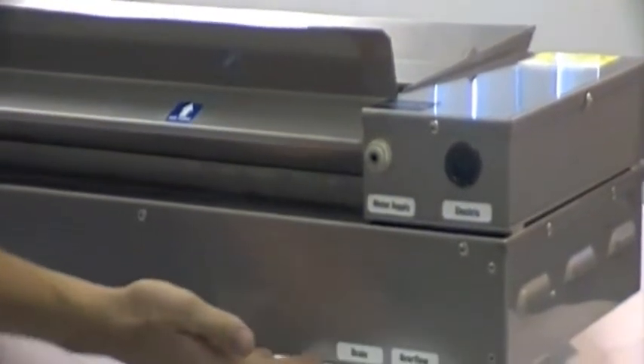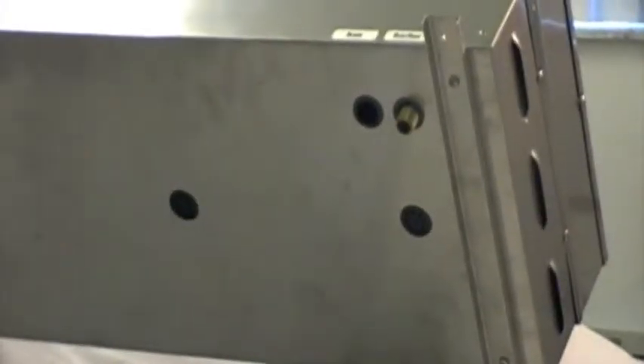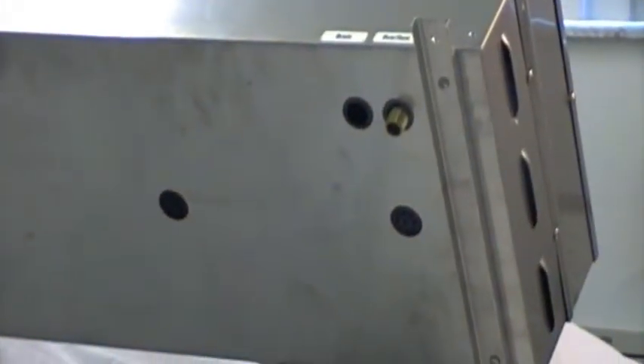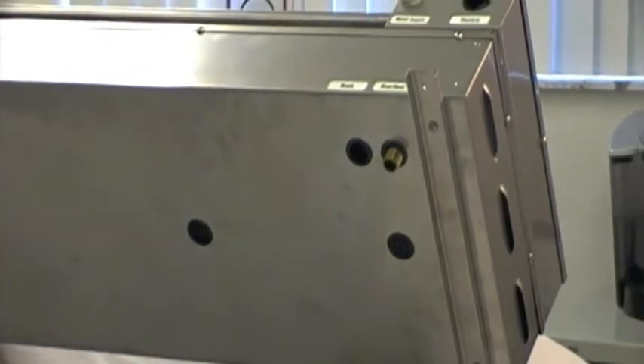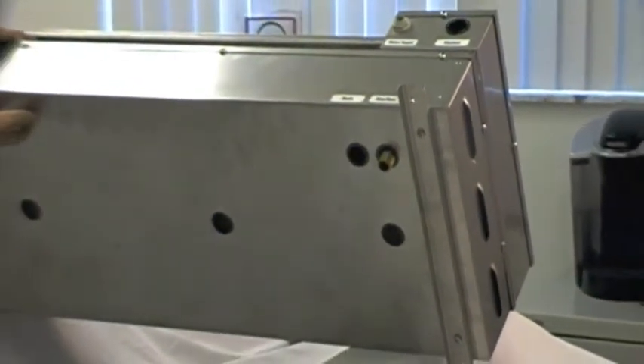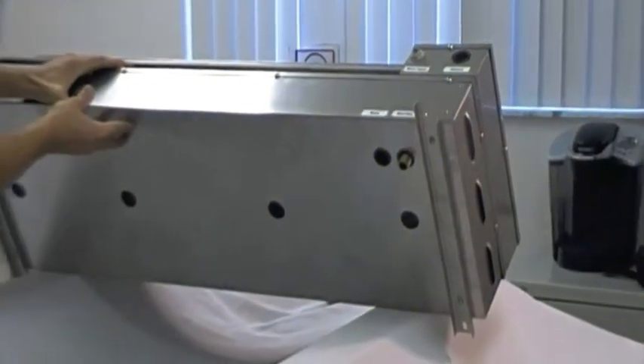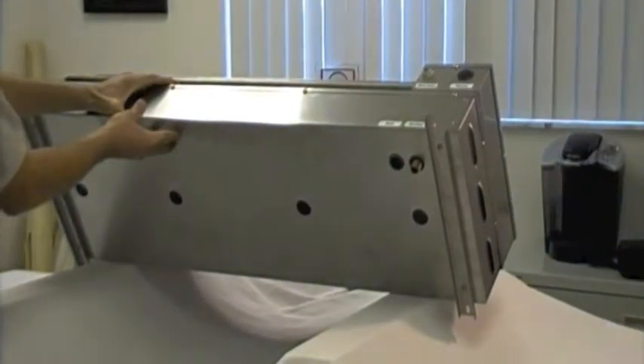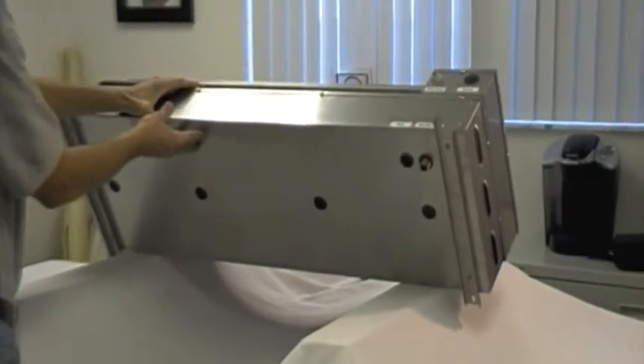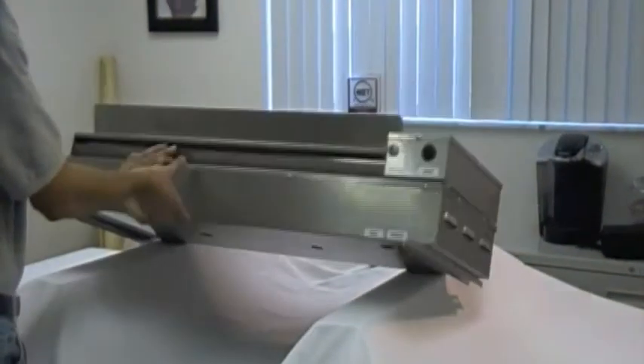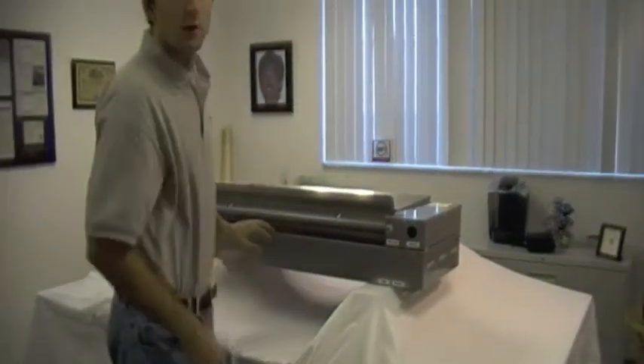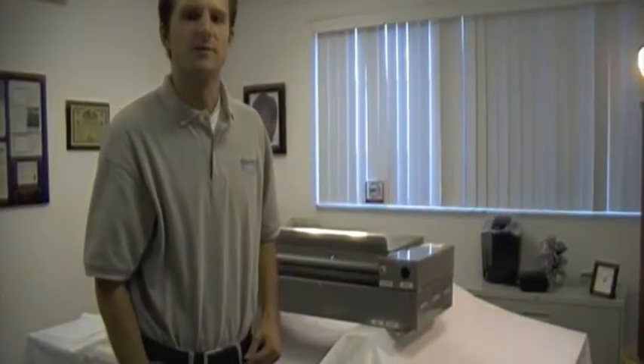There is a drain and overflow located at the bottom of the unit. The overflow needs to be piped away from any humidifiers that are beneath this unit. The drain will be capped unless you want an automatic drain, solenoid valve, or ball valve attached. The humidifiers will use 100% of the water supplied to them. There is no flush cycle unless you would like an auto drain programmed.